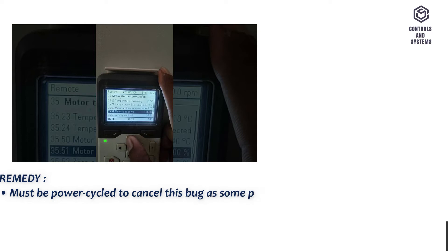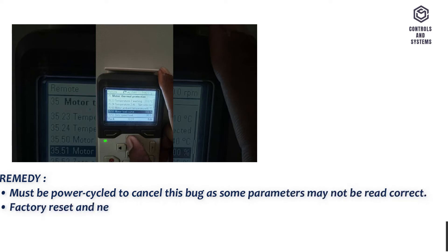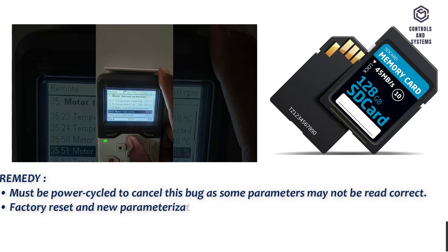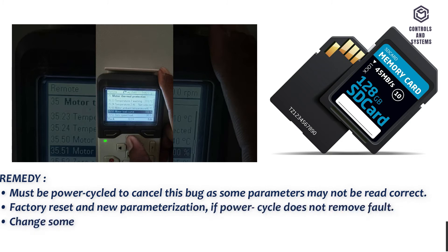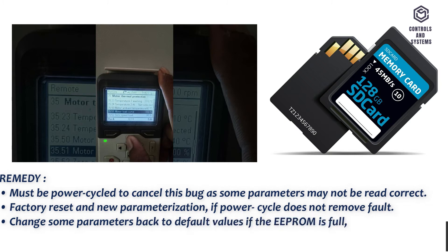Remedy: Must be power cycled to cancel this fault, as some parameters may not be read correctly. Factory reset and new parameterization if power cycle does not remove the fault. Change some parameters back to default values if the EEPROM is full, then power cycle. Change inverter if necessary.